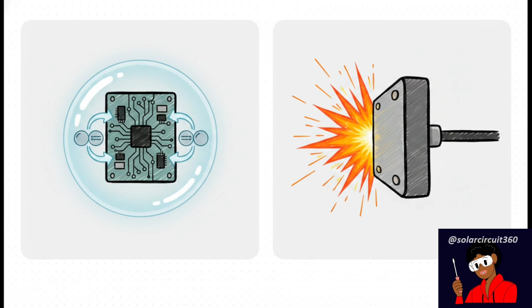During assembly, you really need to understand the distinct, non-overlapping roles of your BMS versus your main fuse. The battery management system is there to protect against unsafe operating conditions, things like overcharging or over-discharging, and it actively balances the cells. But hear me on this, it is absolutely not a replacement for a fuse. The main fuse is there specifically to protect your wiring and your circuits from catastrophic fault currents and dead short circuits. Both of these components are 100% mandatory for a safe system.